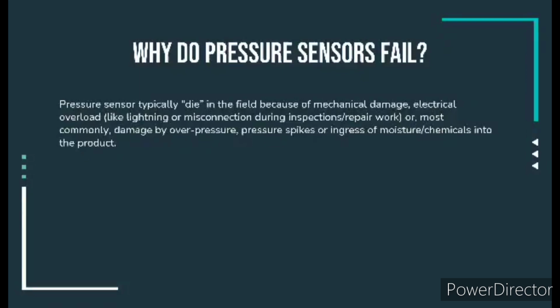Why do pressure sensors fail? Pressure sensors typically die in the field because of mechanical damage, electrical overload like lightning or misconnection during inspections or repair work, or most commonly damage by overpressure, pressure spikes, or ingress of moisture or chemicals into the product.